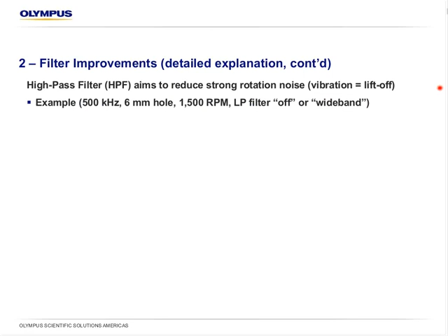So if I have no high pass, basically it's a pretty noisy signal, and we can see in the background, this is obviously the crack signal, and this is the probe motion or rotation or vibration noise. And actually, it's not too bad because it's on a standard. Imagine in the real hole when it gets noisy and a lot of indications occur. So as we increase the high pass to 25, 50, 75, up to 125 hertz, basically the probe is kept at the same position all the time and rotating.